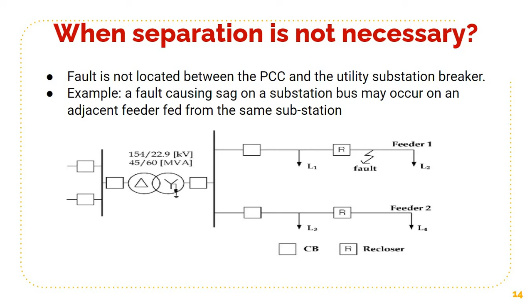So here, when separation is not necessary, this is a case where separation is not necessary. The fault is not located between the PCC and the utility substation breaker. A fault causing sag on a substation bus may occur on an adjacent feeder fed from the same substation. So a fault is occurring in feeder 1, but the effect comes to feeder 2 and feeder 2 gets tripped. So this is not a case where the separation is necessary. Separation is not necessary.